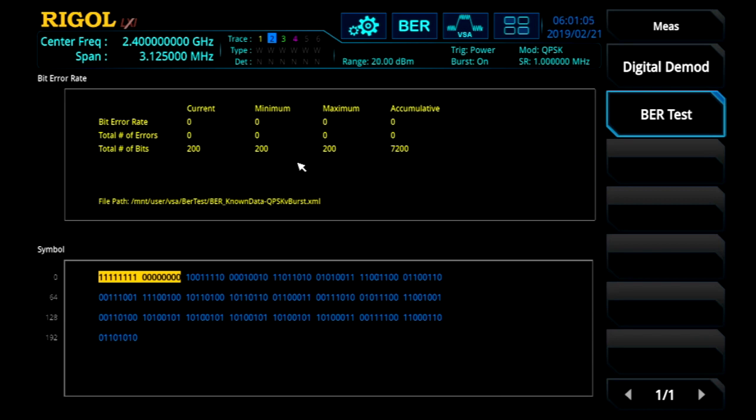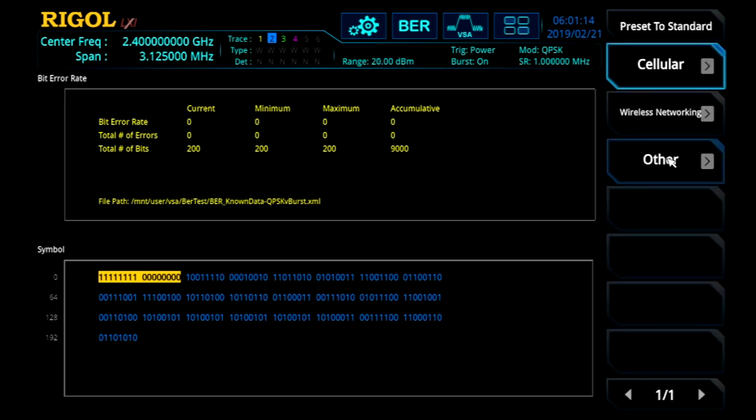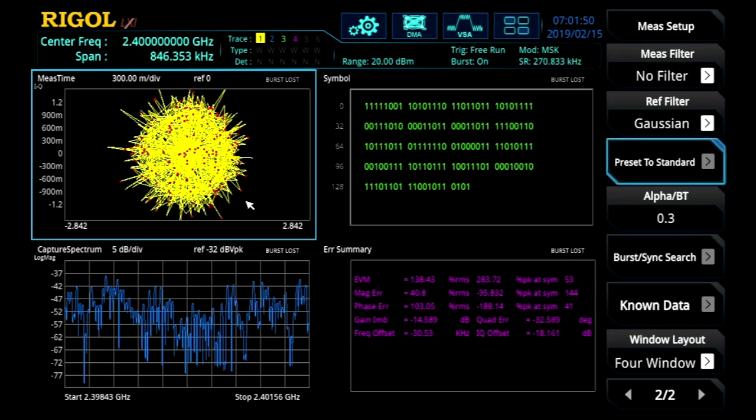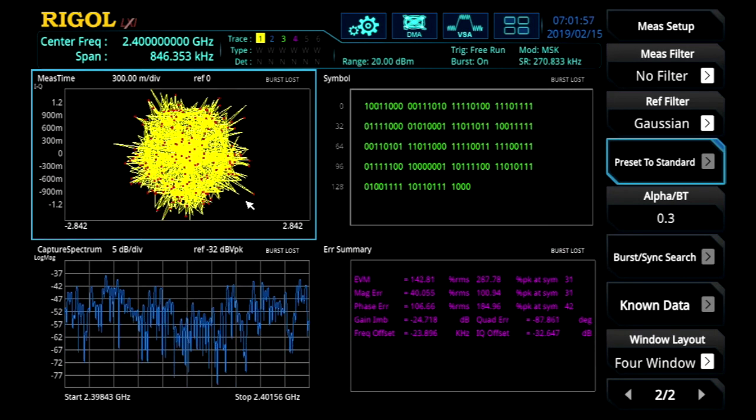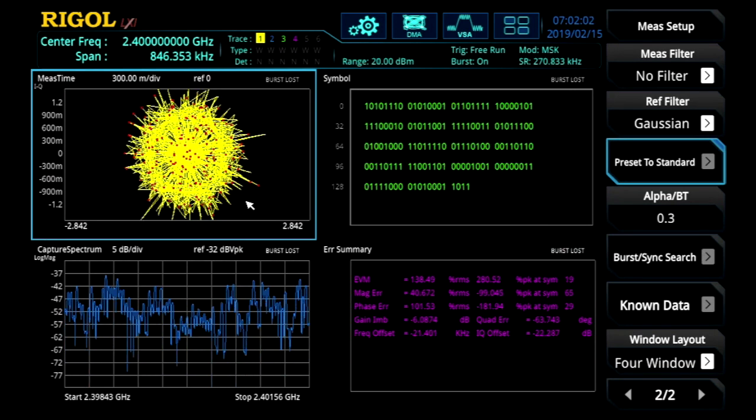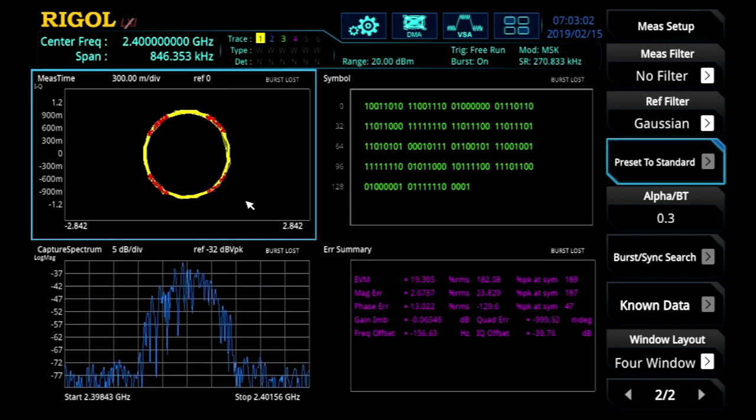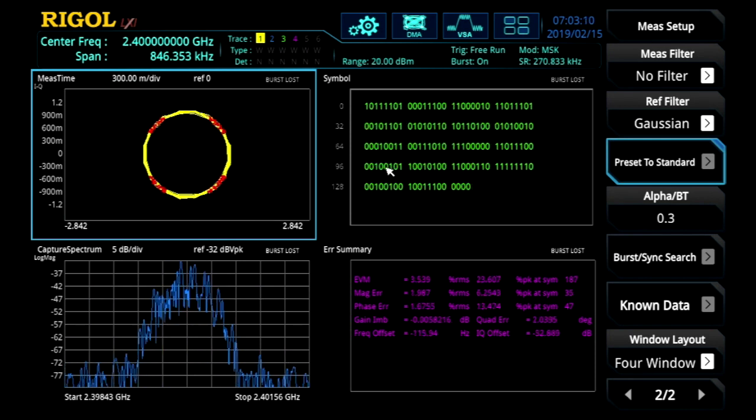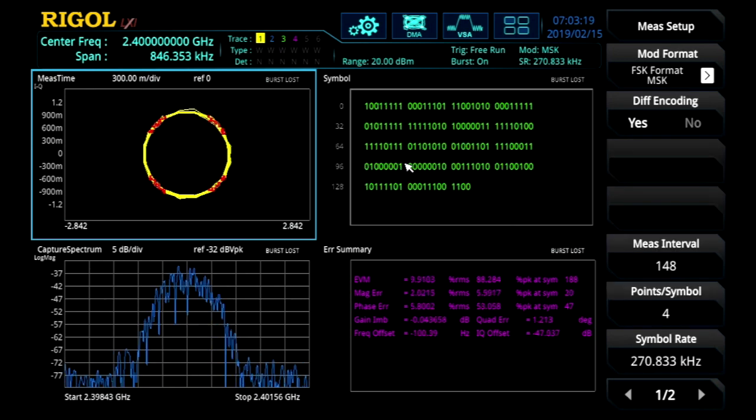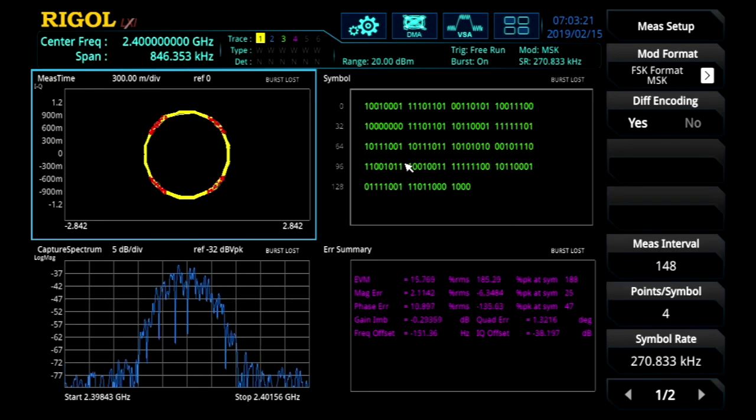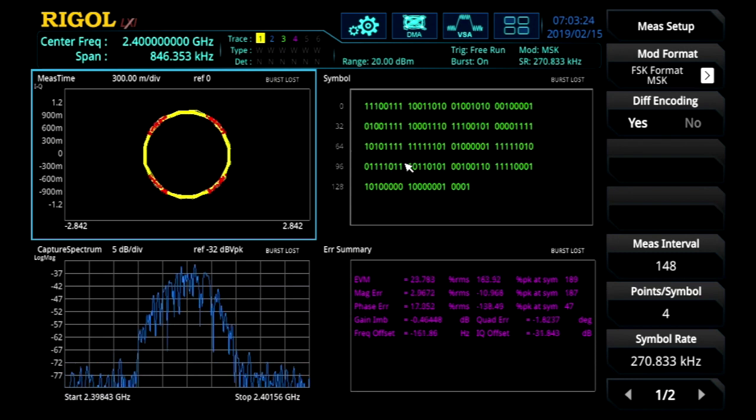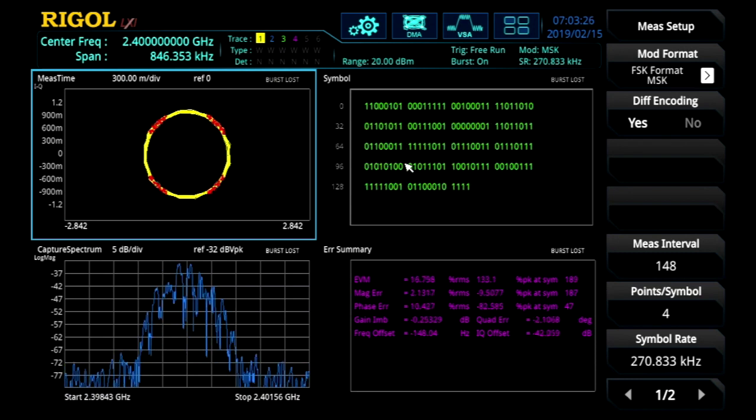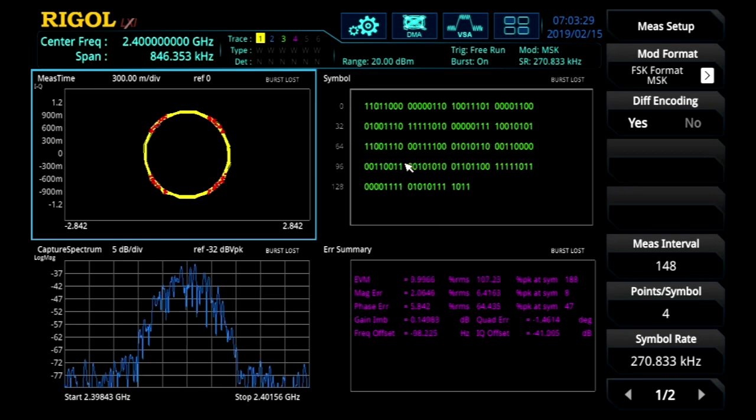In addition, because of all the complicated setup available in this instrument, we can go further and go ahead and preset to some standard test elements. For instance, we can preset to a GSM pulse and then change the data being output by our signal source. So now we're looking at a totally different type of modulation. A GSM uses different filter types and a MSK modulation style at a different frequency. But the instrument is able to preset to these standards so the GSM pulse and data can be easily identified.